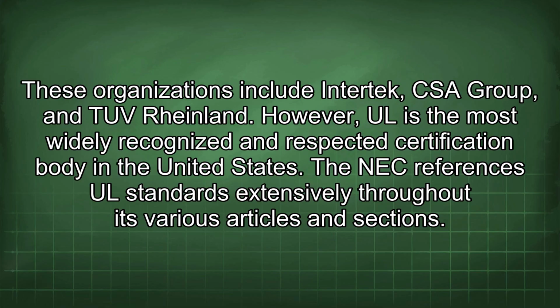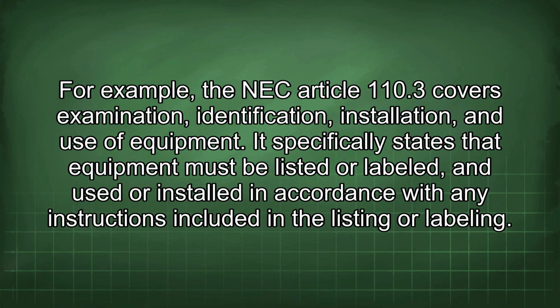The NEC references UL standards extensively throughout its various articles and sections. For example, the NEC Article 110.3 covers examination, identification, installation, and use of equipment. It specifically states that equipment must be listed or labeled, and used or installed in accordance with any instructions included in the listing or labeling.